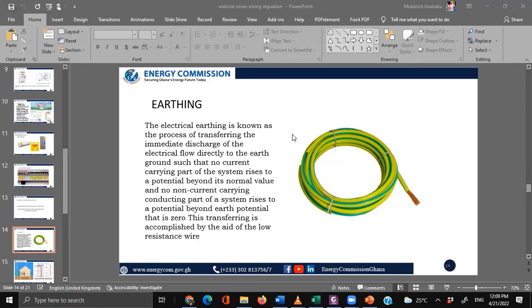Why do we have to employ earthing? Here's a simple way to know an electrician has installed an earthing system: in our trainings we always advise using the correct cable sizing and correct cable colors. Green and yellow denote an earthing cable, whether it's a 1.5 from the lighting circuit or a 2.5 from the socket circuit—wherever there is earthing, it should be a green and yellow cable.